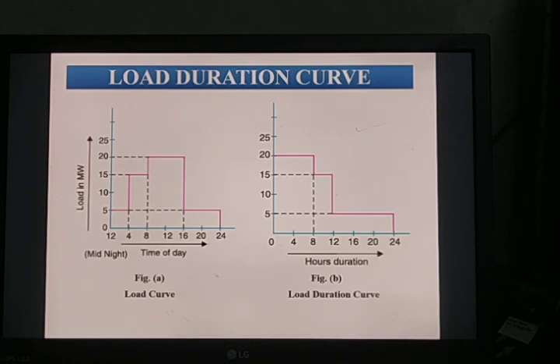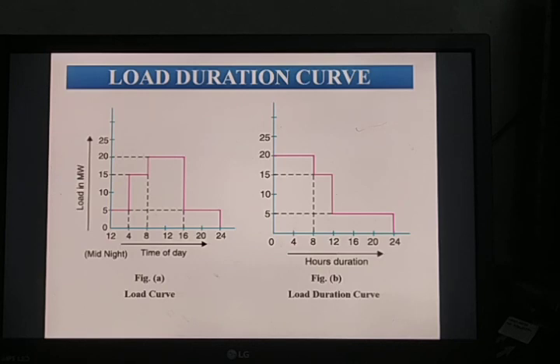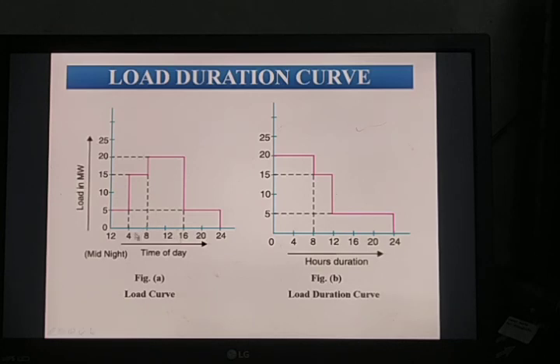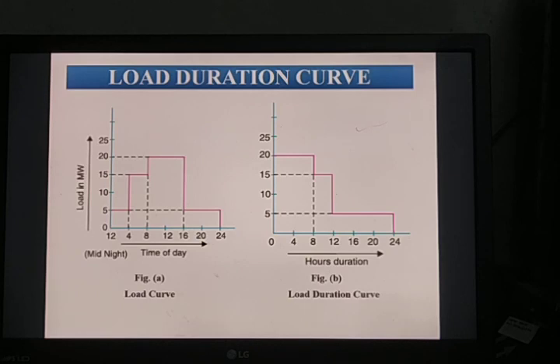We can measure the load at early morning 4 o'clock, 8 o'clock, 12 o'clock, or afternoon 2 or 4 PM — at any time we can measure how much load variation is available. We can also note down the maximum and minimum load on the power station. In this load curve, at 8 o'clock the load is 15 megawatt; after that it slightly increases to 20 megawatt for the remaining 8 hours. The area under the curve gives the number of units generated in a day, and we can also calculate how much coal is utilized.